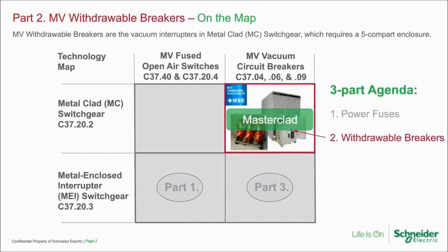Part 2 follows the same format: map, NEC, pros and cons, and limitations. Now we're moving into metal clad and a much higher degree of enclosure regulation — specifically down to the sheet metal in some cases. This category is where the breakers live, traditionally. There's a very specific requirement for compartmentalization: five compartments. For example, the breaker has its own compartment and the busing its own compartment. This is distinctly different from metal enclosed interrupters, which basically have no requirement for compartmentalization.